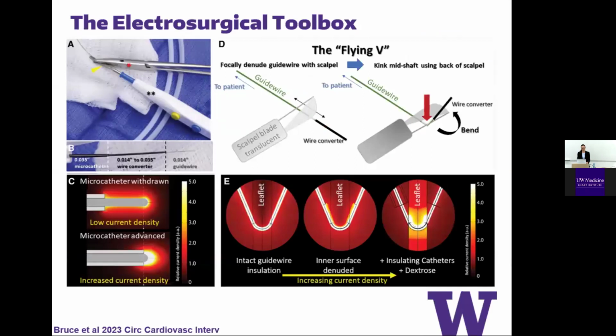So this is what the current electrosurgical toolbox looks like. The cutting element is a guide wire, which happens to be conductive and is typically coated in a polymer coating that serves to facilitate guide wire delivery in coronary interventions, but also happens to be an electrical insulator. And so it can be used to deliver current to a specific location to achieve tissue cutting. Guide wires are then further, for this purpose, sheathed in plastic microcatheters and guides to improve insulation and maximize current density at the intended site.